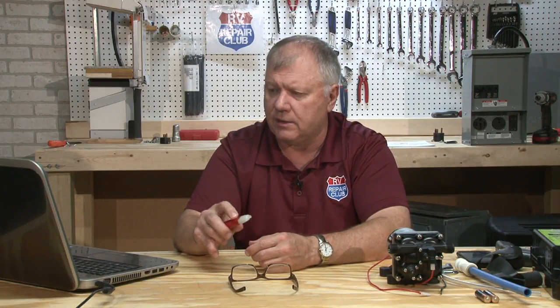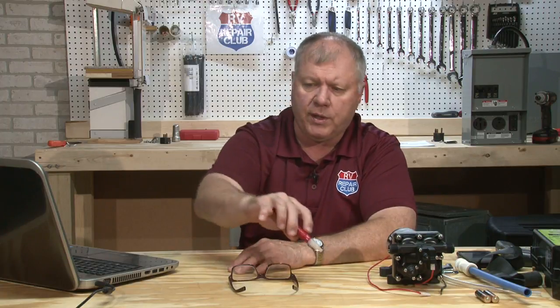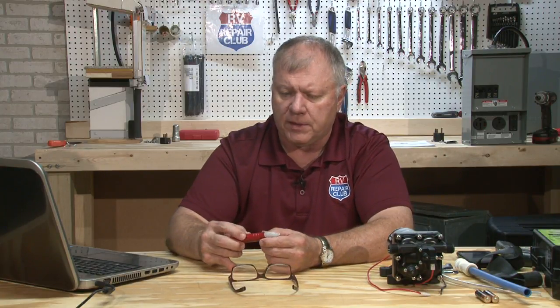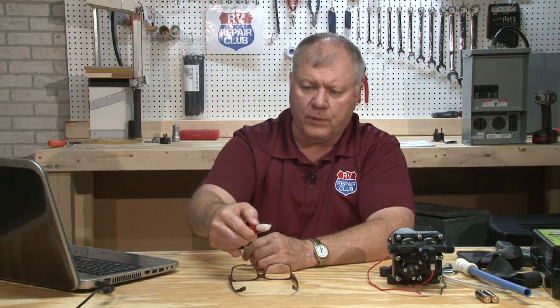It's a non-contact voltage tester, and you just put it up to wherever you have electrical cord, and it'll register. The only problem is that when I get by a GFCI outlet, there's enough stray voltage coming off it, it's going to show me voltage on both sides, even if there's not.